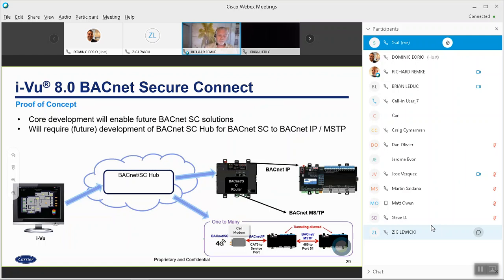If you've got a customer that has a large campus and their network spans multiple networks, or maybe even they use a VPN to connect, and they're concerned about BACnet broadcasts, and somebody like a school, maybe somebody trying to get in and hack the BACnet communication, because it is sort of open. You can see what's going on with BACnet, and you can see the broadcasts. Well, BACnet Secure Connect will fix all that.